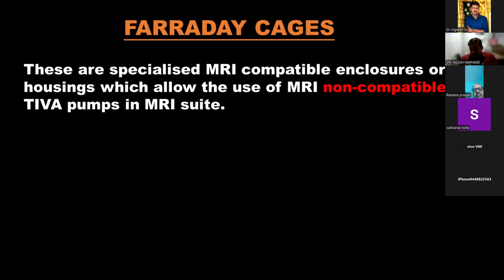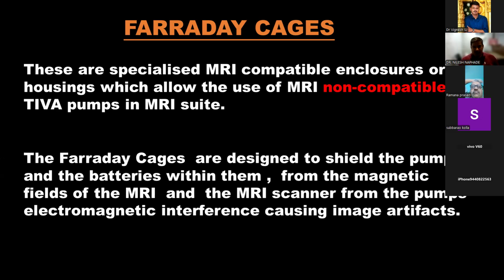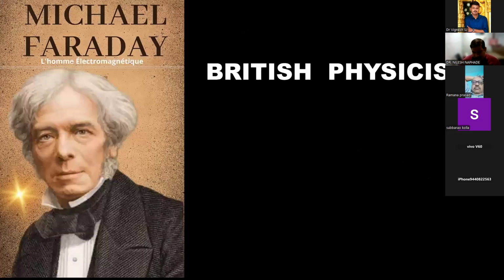Faraday cages are specialized MRI compatible enclosures or housings which allow the use of MRI non-compatible TIVA pumps in MRI suite. Once the TIVA pump is placed in that cage, inside that enclosure, then it can be kept next to the MRI also. And the MRI magnetic field does not impact the performance of the TIVA pump. And the TIVA pump electromagnetic currents and induction motors does not impact the MRI image. The Faraday cages are designed to shield the pump and the batteries within them from the magnetic fields of the MRI and the MRI scanner from the electromagnetic interference coming out from the TIVA pump.